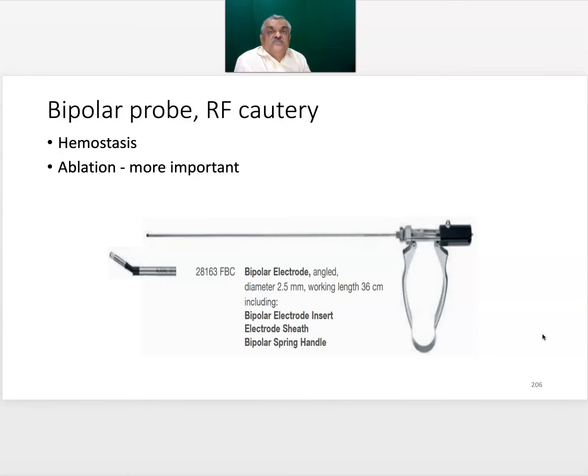neural tissue. This is a bipolar probe or a cautery handle. This is held in the hand of the surgeon. When you press this together, the bipolar probe comes out here. The one electrode is at the tip and the second is on the side. This white is an insulating ring, and this insert can be removed. This sheath can be removed.